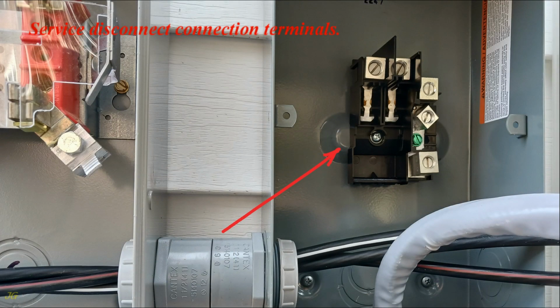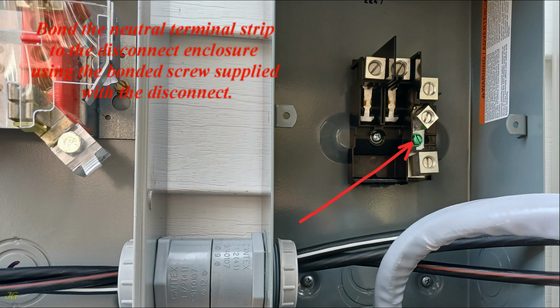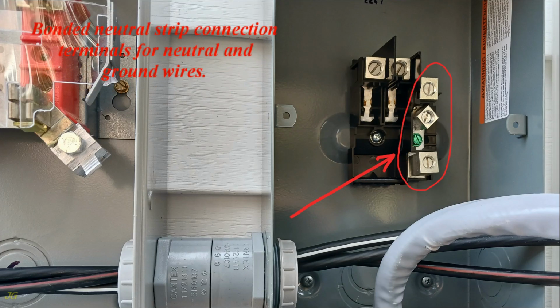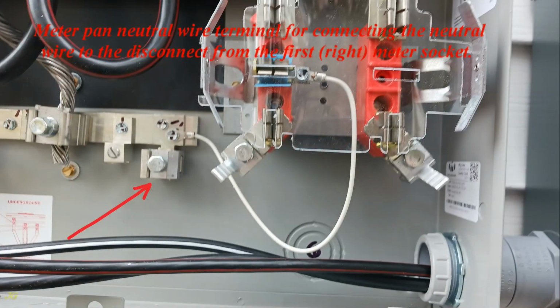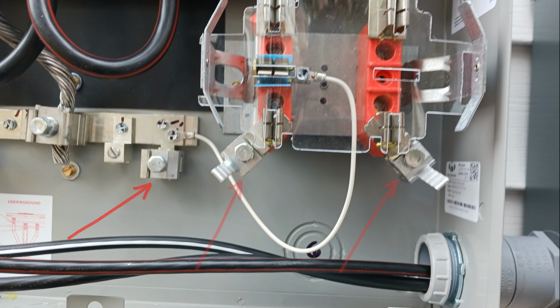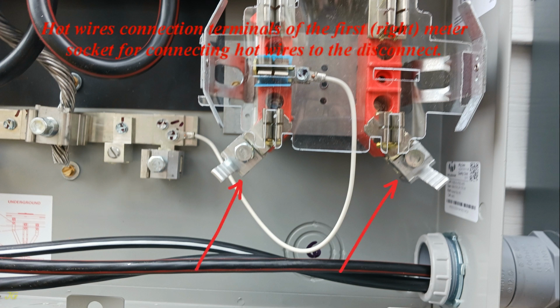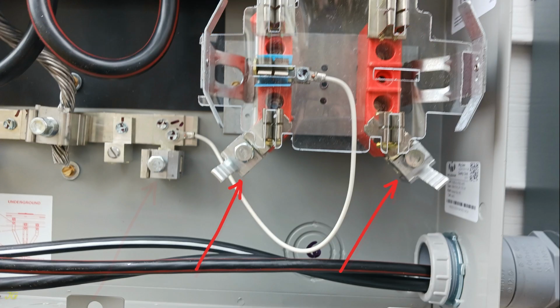Service disconnect connection terminals. Bond the neutral terminal strip to the disconnect enclosure using the bonding screw supplied with the disconnect. Bonded neutral strip connection terminals for neutral and ground wires. Connection terminals for hot line wires from the meter pan. Meter pan neutral wire terminal for connecting the neutral wire to the disconnect from the first, right, meter socket. Hot wires connection terminals of the first, right, meter socket for connecting hot wires to the disconnect.